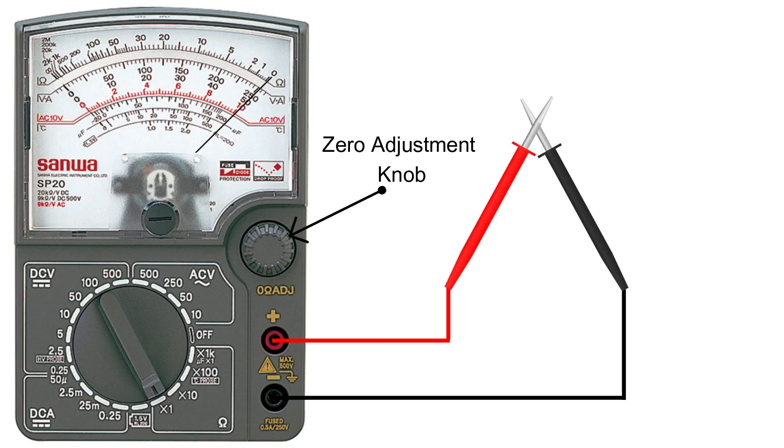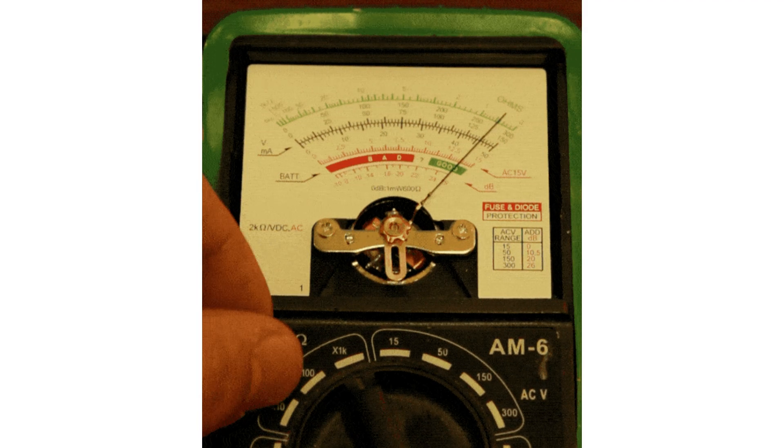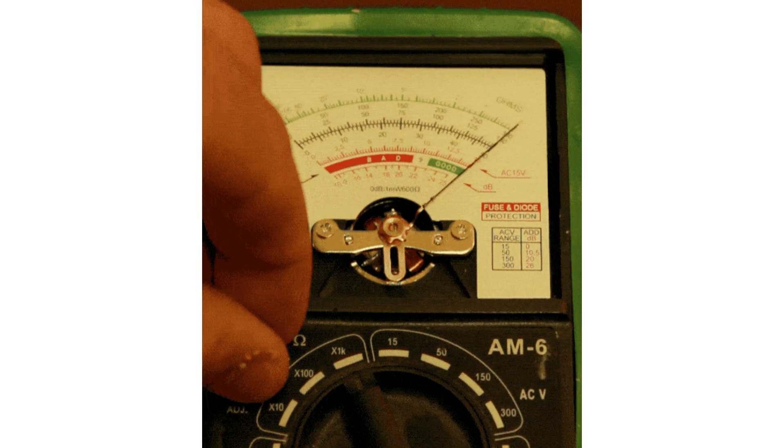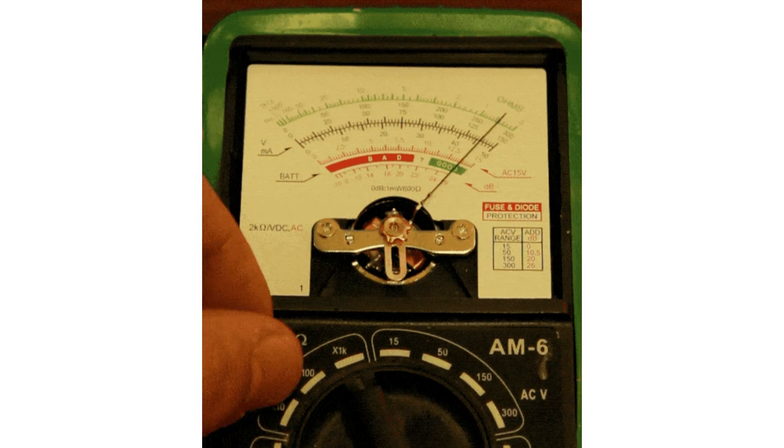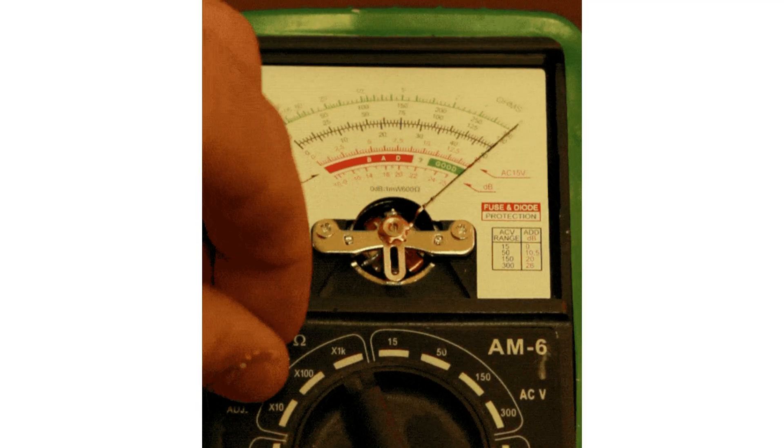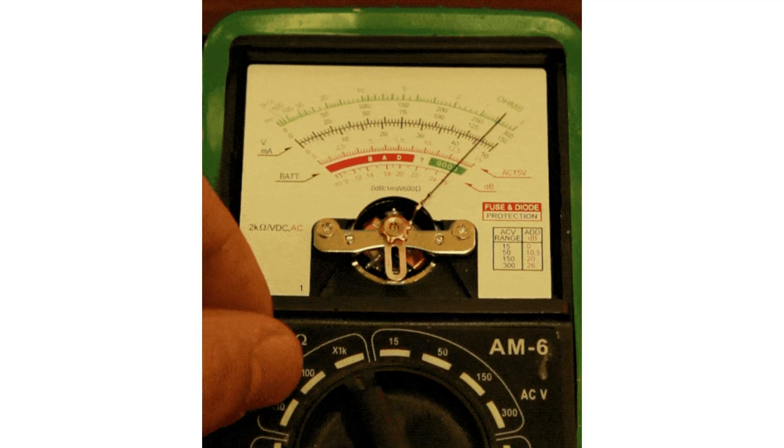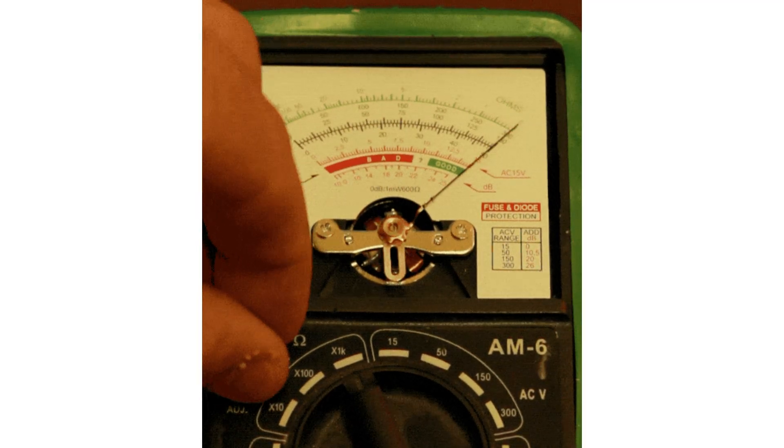Now short the two probes together. The needle should swing all the way to zero on the right. If it doesn't, use the zero adjustment knob to set it perfectly. This step is really important every time before measuring.